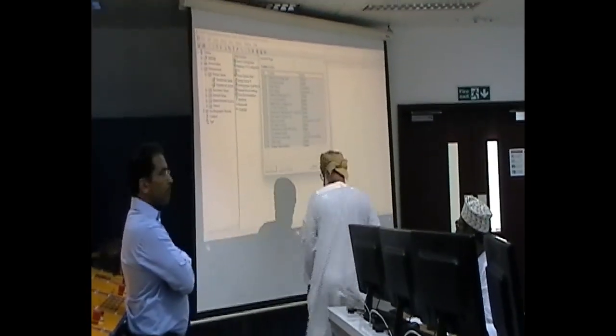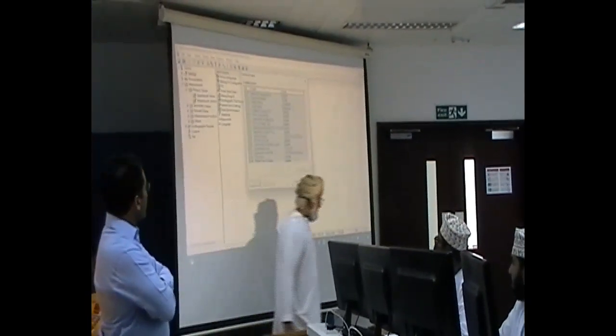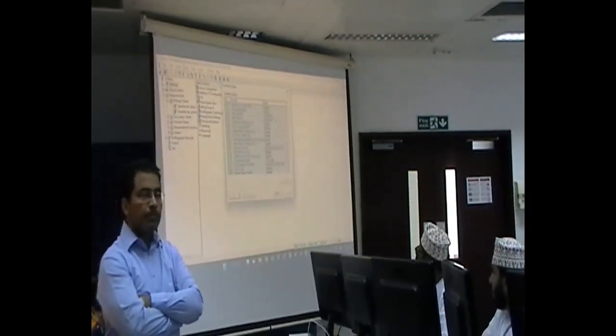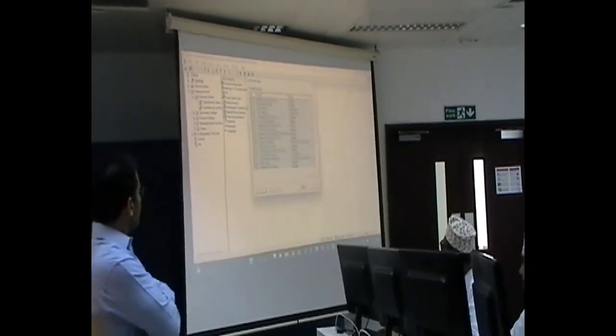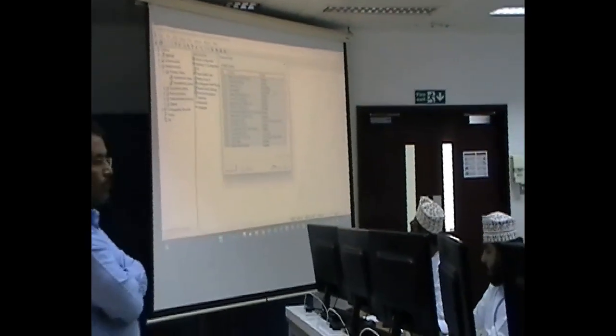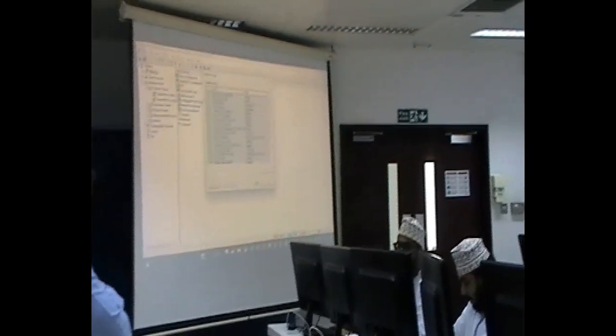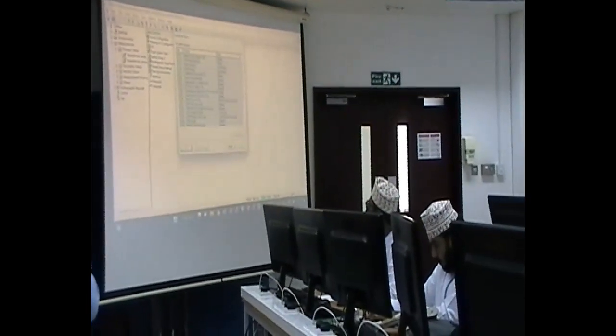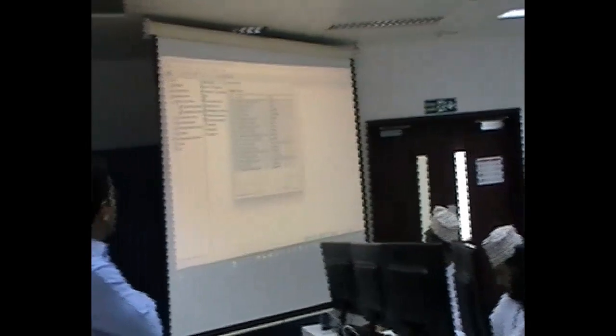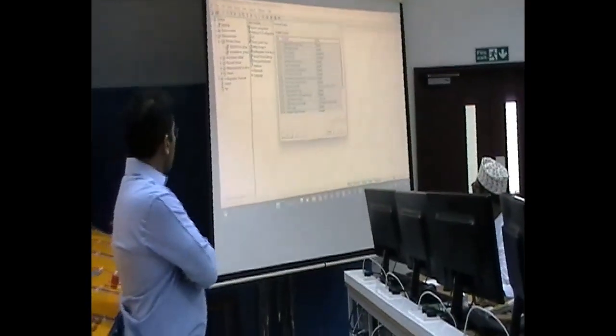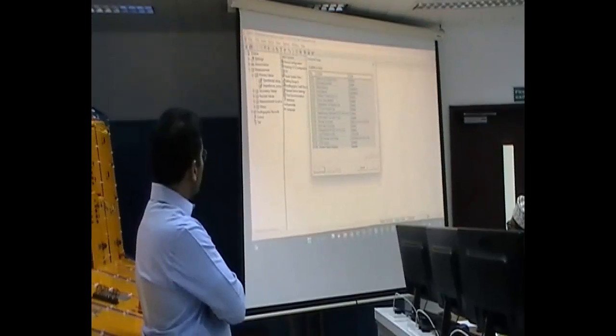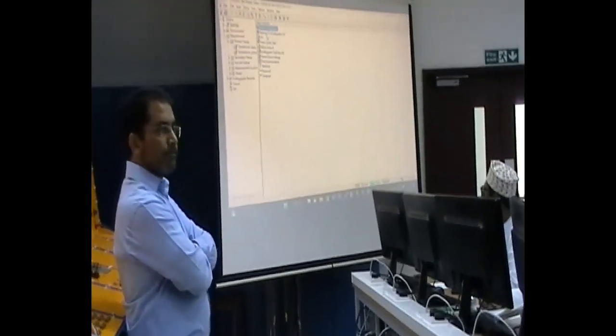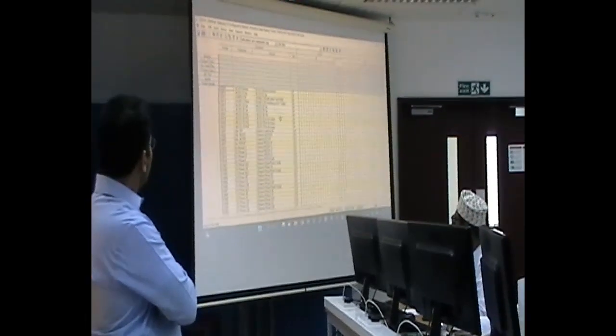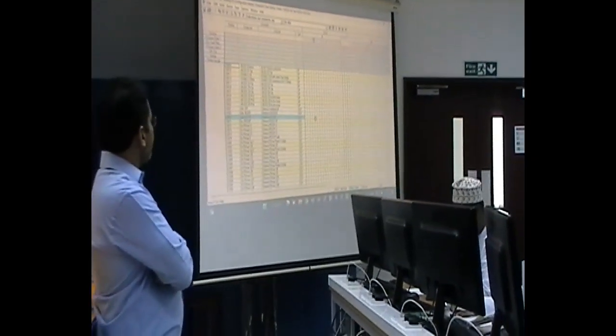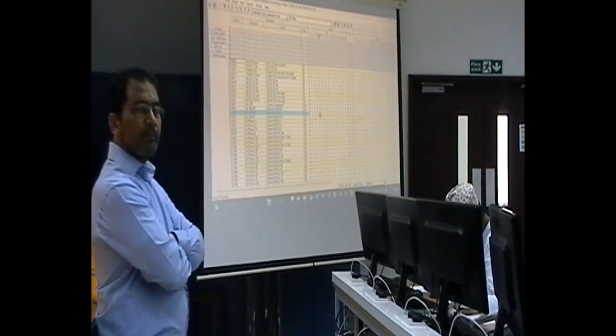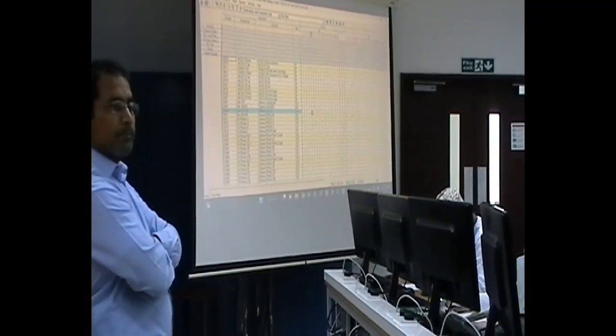What is the characteristic of the relay here? Quadrilateral. We could have more characteristics or even some other. We always use quad nowadays for the phase and for the earth. I could have overcurrent or any other function enabled here. Here I can change it always, depending on whatever I want to enable. I have the masking. The masking is configuration of the input, output, LED in the relay, and whatever external signals go out from the relay.